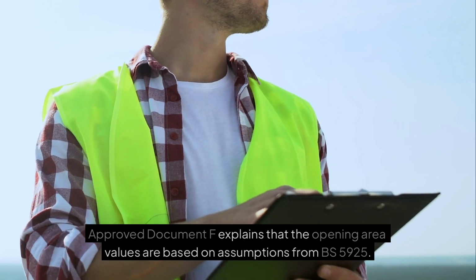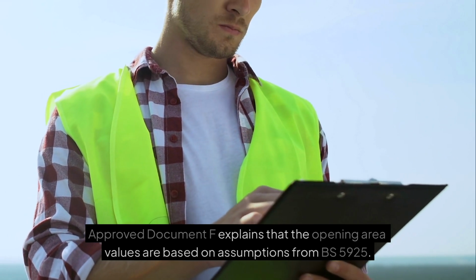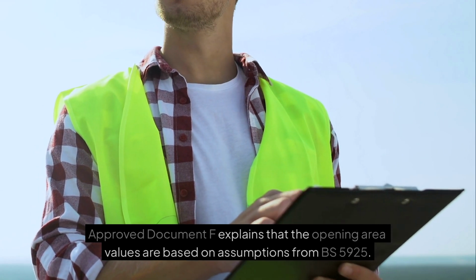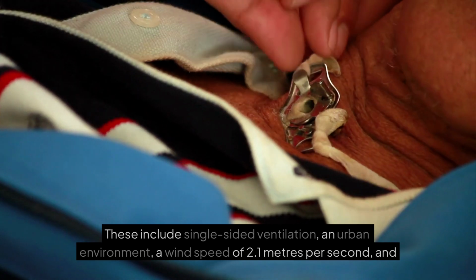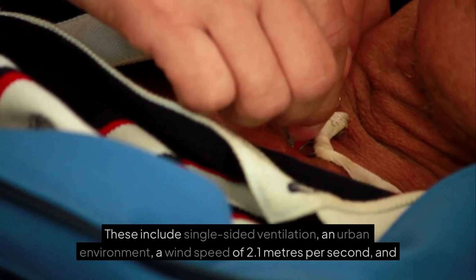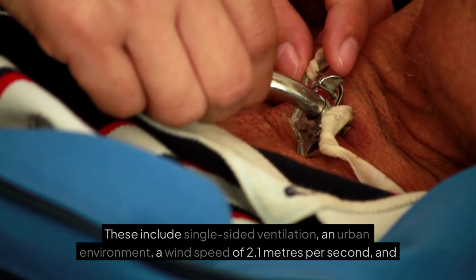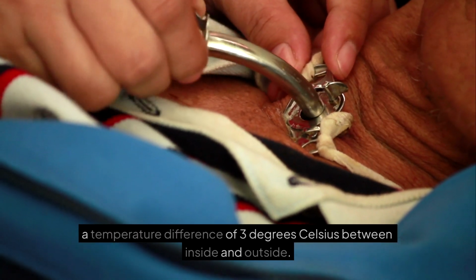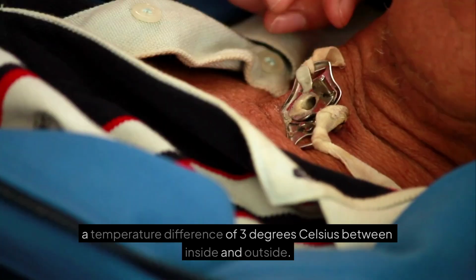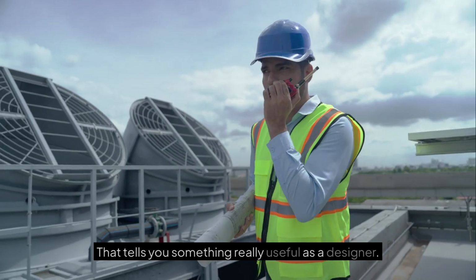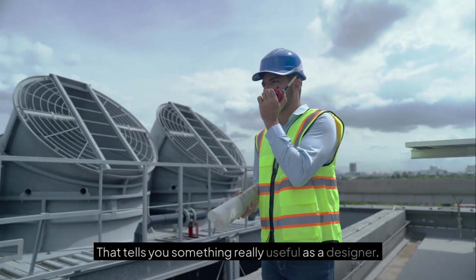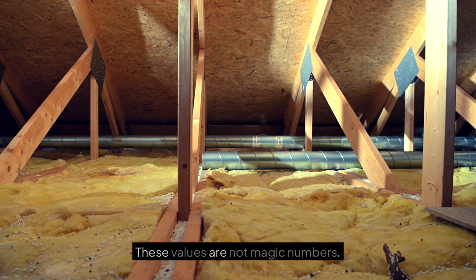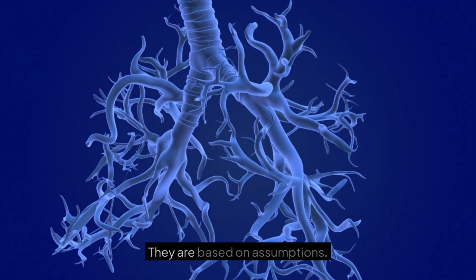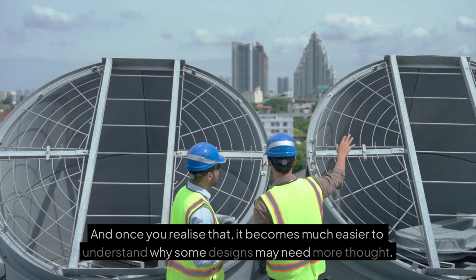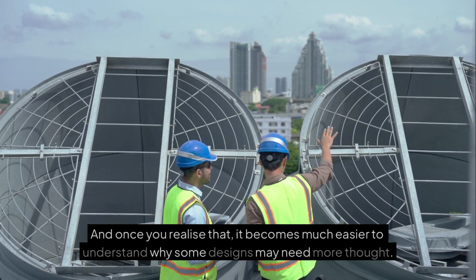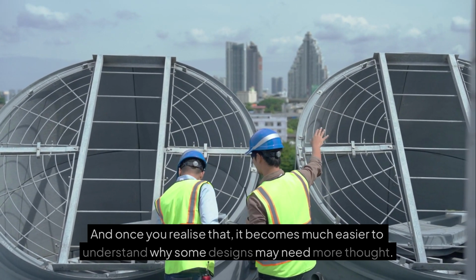Approved Document F explains that the opening area values are based on assumptions from BS 5925. These include single-sided ventilation, an urban environment, a wind speed of 2.1 meters per second, and a temperature difference of 3 degrees Celsius between inside and outside. That tells you something really useful as a designer. These values are not magic numbers, they are based on assumptions. And once you realize that, it becomes much easier to understand why some designs may need more thought.